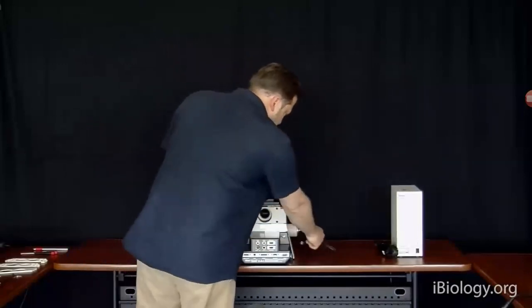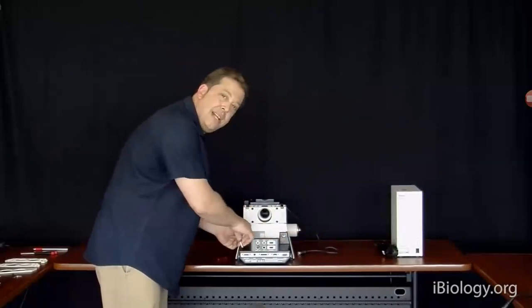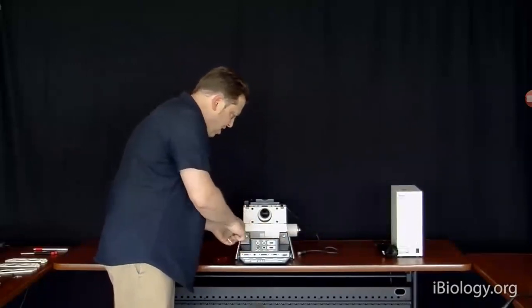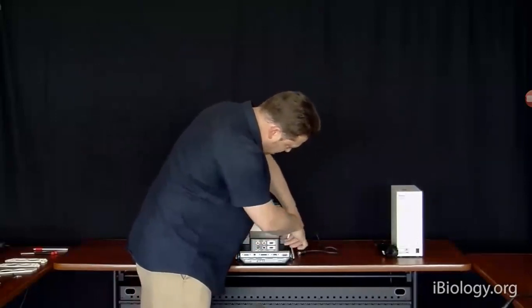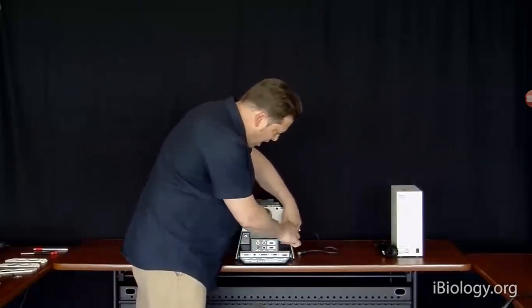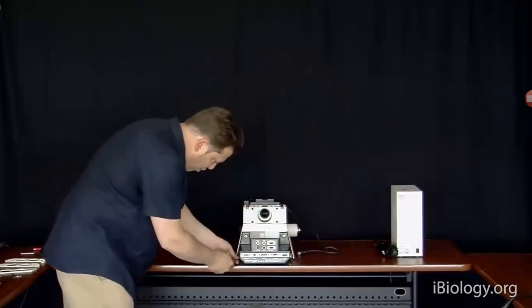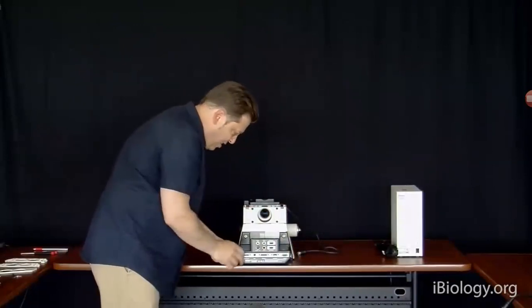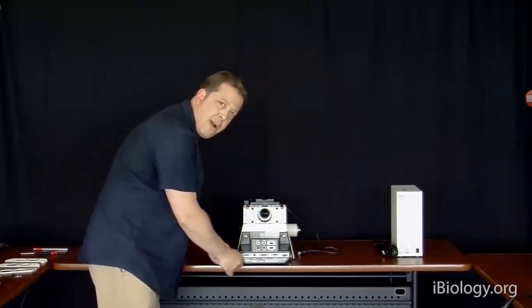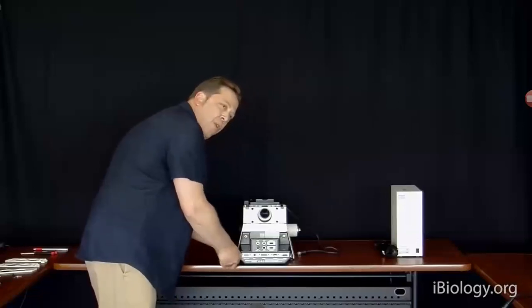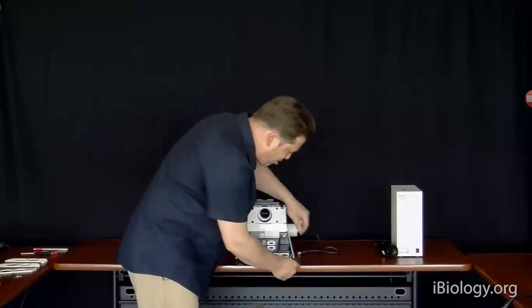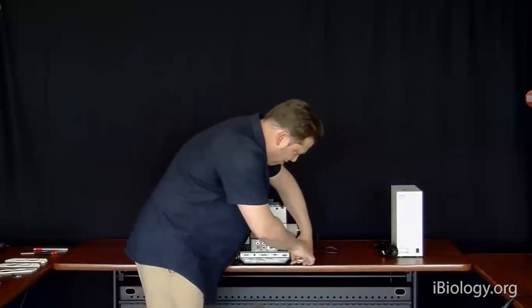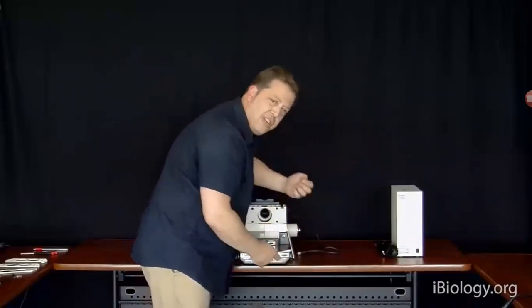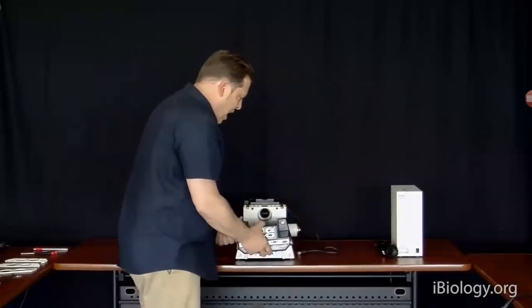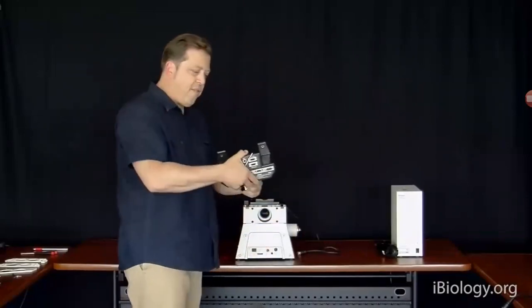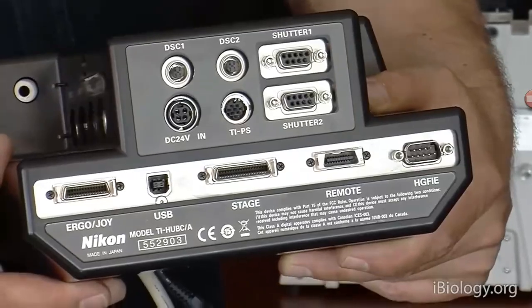This is what we call the hub controller on the microscope. And basically, it's the brains of the microscope. It takes all of the components in the microscope that are motorized and synchronizes them and controls them. And what we would do normally is, with our software, send a recipe for an experiment, say, take one channel image, move a filter, take another channel image, move another filter, and so on, opening and closing shutters for transmitted light, epifluorescence. And we can send all that information to onboard memory storage within this hub controller.